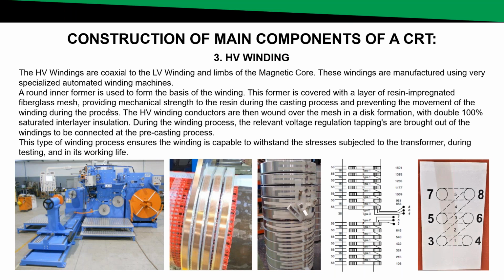The mesh actually acts as rebar for concrete for the resin. So it just adds mechanical strength and reduces cracking of the resin under normal operating conditions. The HV winding conductors are then wound over the mesh in a disc formation with double 100% saturated interlayer insulation. During the winding process, the voltage regulation tappings are also brought out to be connected at a later stage. This type of winding process ensures windings are capable of withstanding the stresses subjected to the transformers during the testing and its working life.